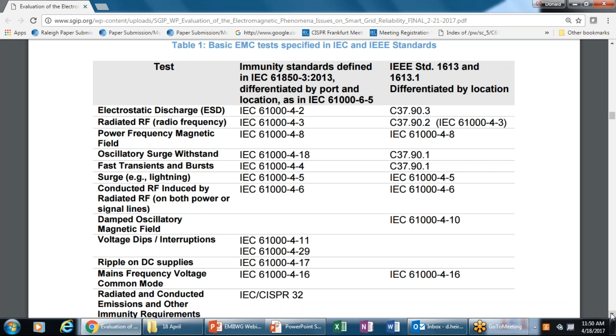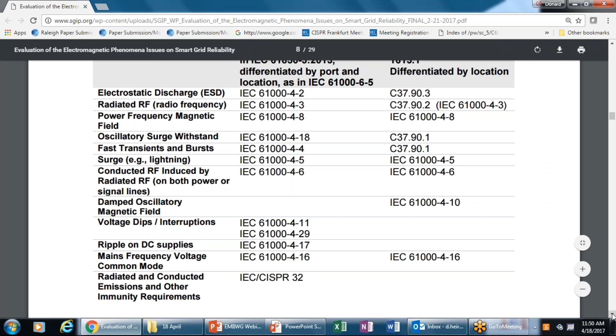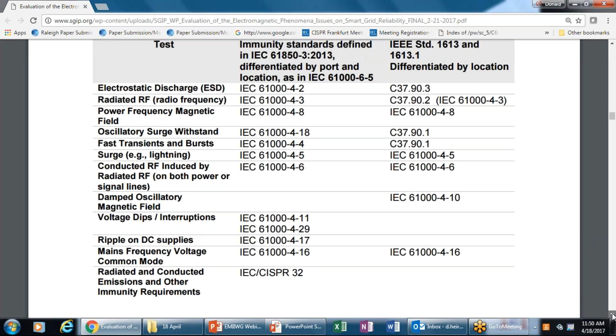And you can see in some cases there are no equivalents on both sides. For example, 61850 has nothing on damped oscillatory magnetic fields, where 4-10 does, and that's covered in IEEE standard 1613.